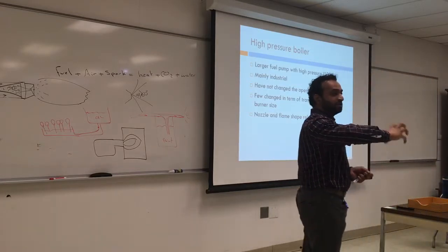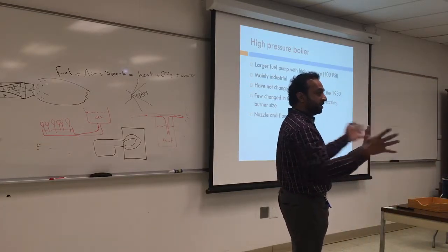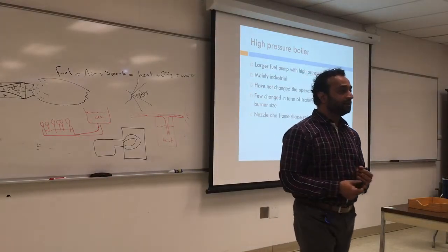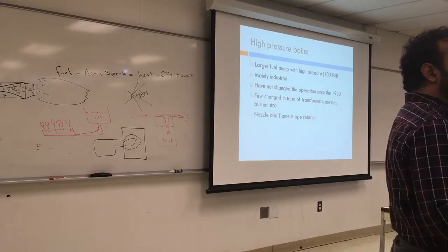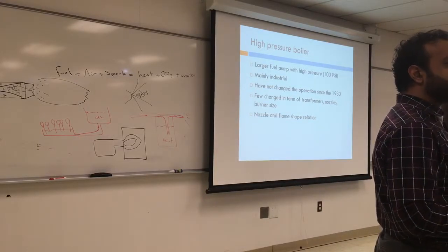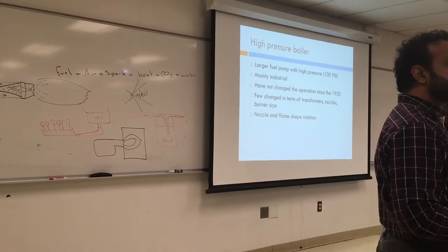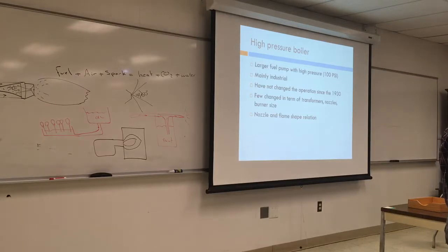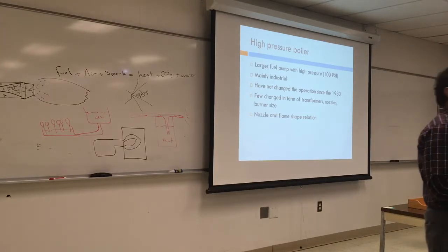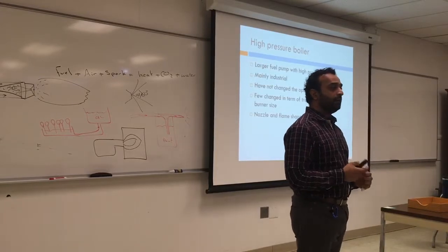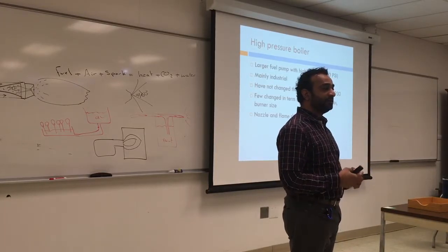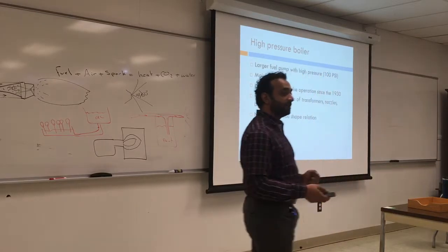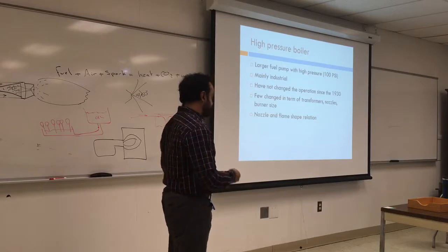If you switch the distance, it will change the shape. So the same thing happens here with the nozzle. The nozzle is very sensitive. If you drop it, then you have to change it. Try not to touch it with your hand because you don't want some oils in it. If it's scratched up, it will screw up the angle, so you don't want that. And also the strainer inside should always be clean. And every time we do maintenance or preventive maintenance or checkup or tune-up, you have to change the nozzle. They're not expensive, and sometimes they work, but they don't give you the right spray.